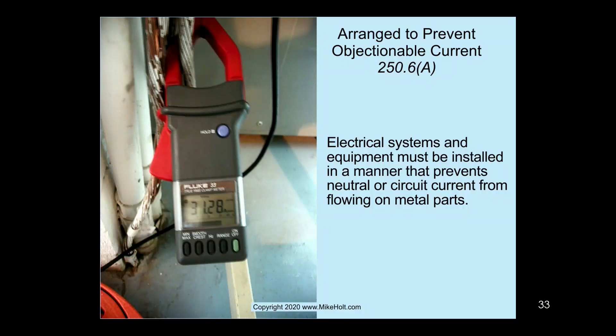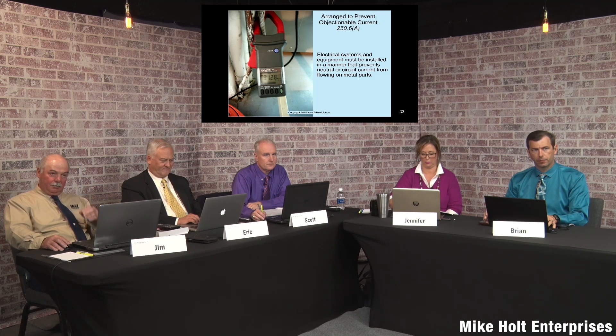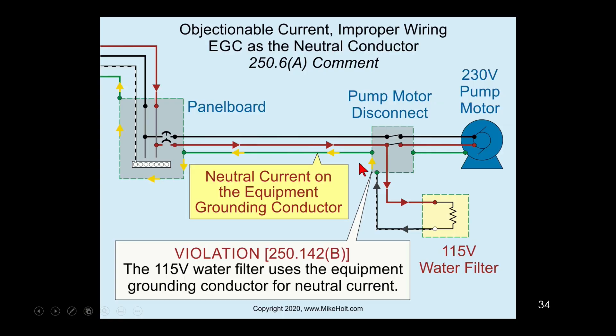Here's a meter showing what might be considered an effective ground fault current path — you can see 31.28 amperes on these bonding conductors. These bonding conductors are only there in the event of clearing a fault; they're not there to be used as a circuit conductor. If you put an amp meter on any equipment grounding conductor in a panel and it's carrying current, that's a problem. That wire is just sitting there waiting in the event of a fault — it's not supposed to be carrying current.